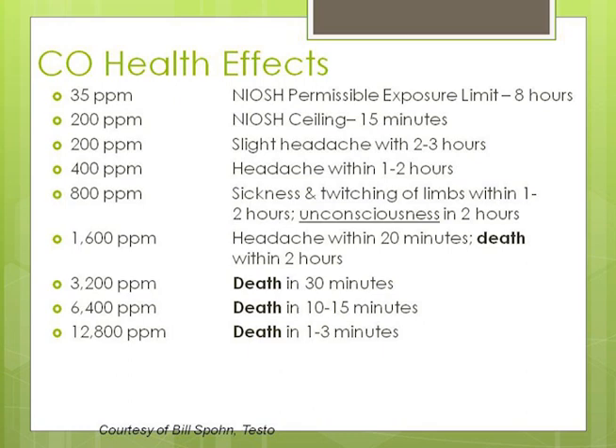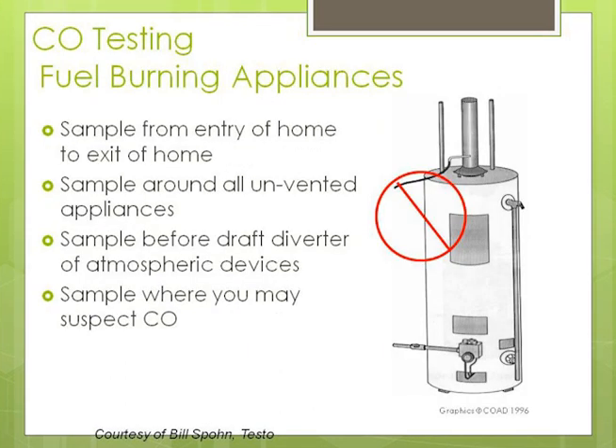When testing for carbon monoxide, you sample at the entry of the home, around all unvented appliances, and before the draft diverter of atmospheric appliances. The draft diverter — that little hat on the hot water heater — is supposed to funnel flue gases into the flue and take them away. You also sample anywhere else you'd expect to find carbon monoxide.